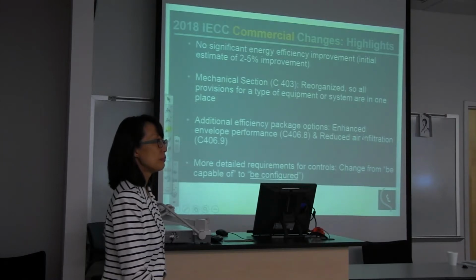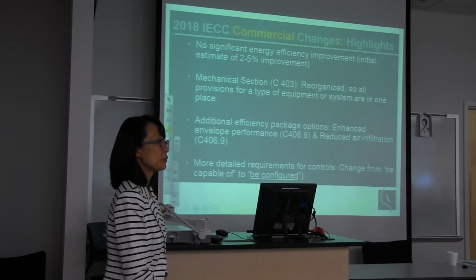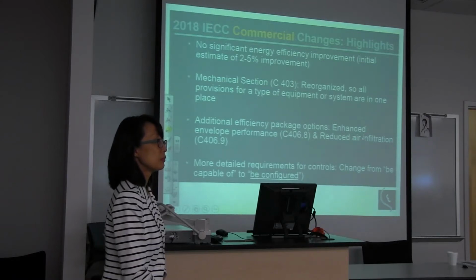Semi-heated is not a classification in IECC, that's an ASHRAE 90.1-only classification. So how do you deal with the sprinkler system and having enough heat in the building just to keep the sprinklers from freezing?